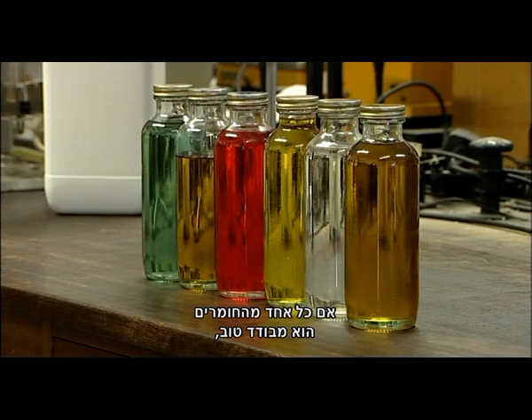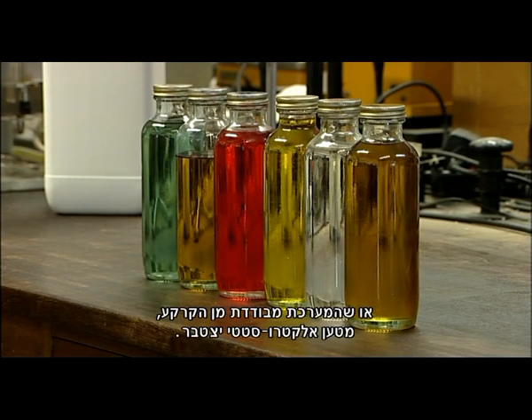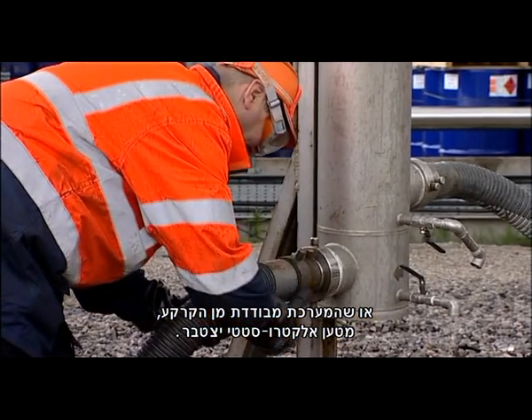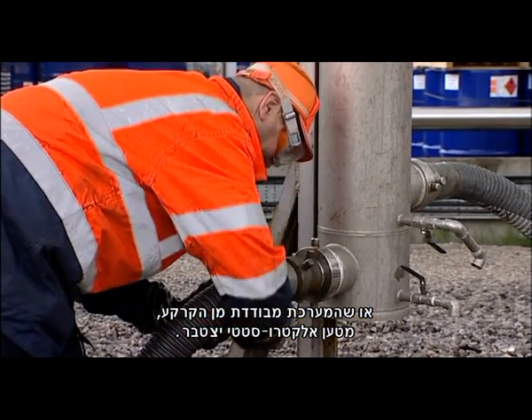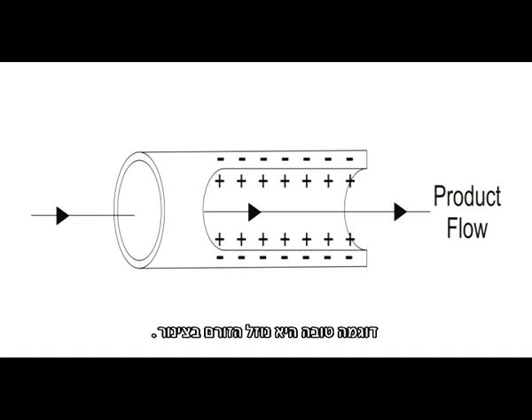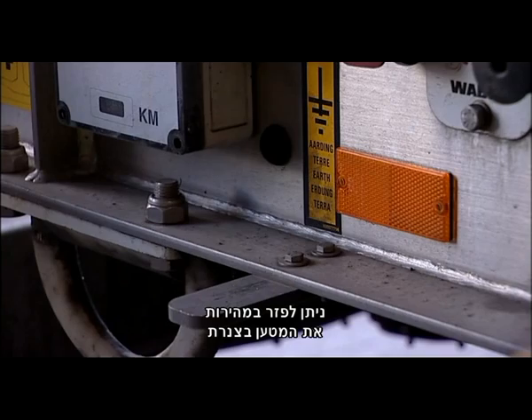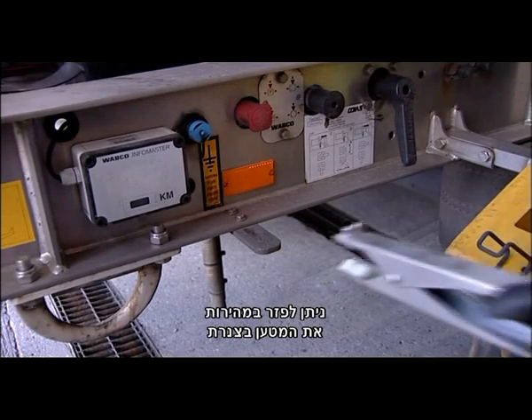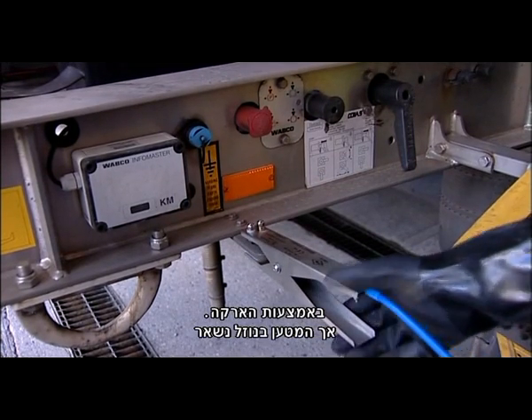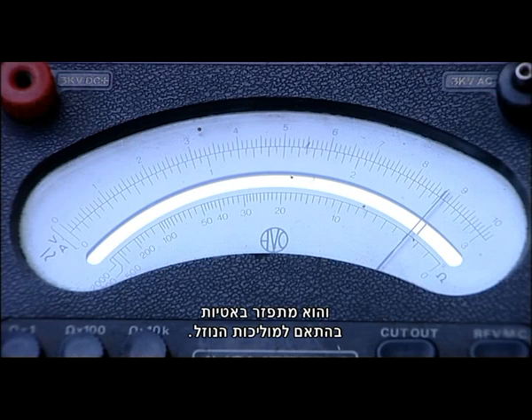If either of the materials is a good insulator, or the plant is isolated from earth, electrostatic charge will accumulate. A good example is liquid flowing through a pipe. Negatively charged electrons move across the boundary between the two bodies and are then unable to return. The charge on the containment system can be dissipated quickly by earthing, but the charge in the liquid remains and is slowly dissipated, depending on the conductivity of the liquid.